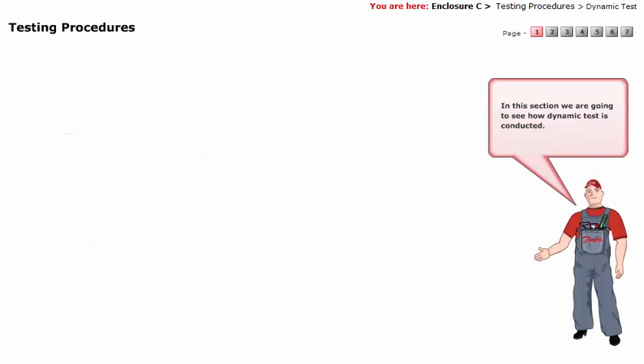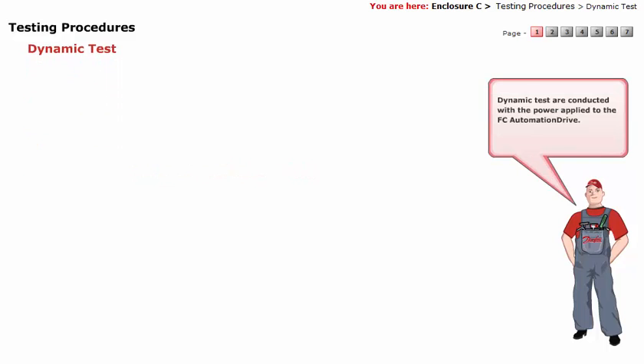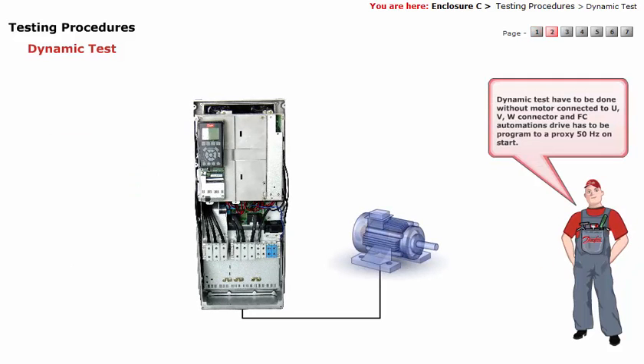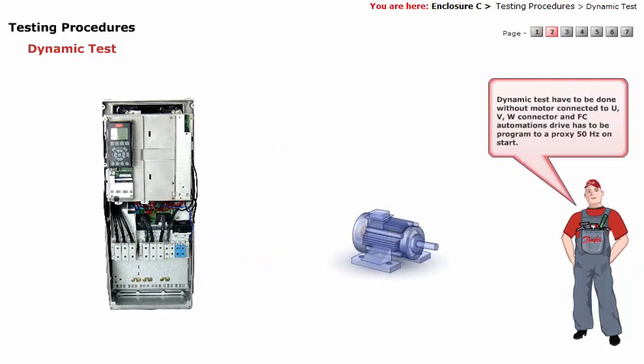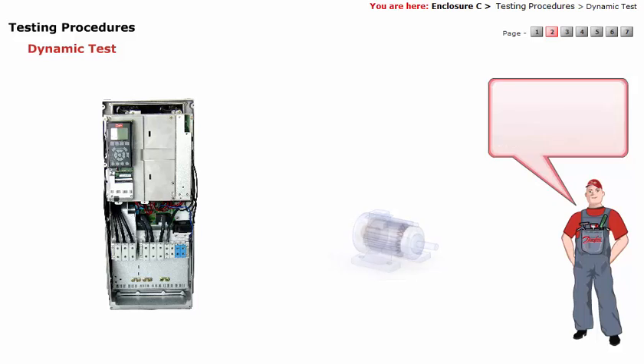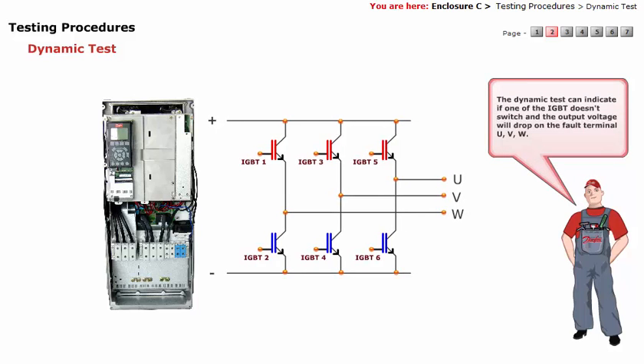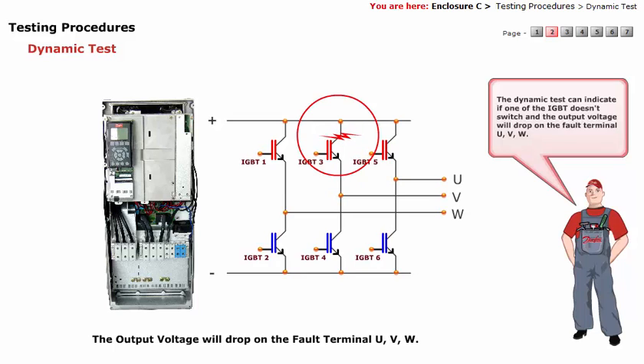In this section, we are going to see how dynamic test is conducted. Dynamic tests are conducted with the power applied to FC automation drive. Dynamic tests have to be done without a motor connected to the UVW connector, and the FC automation drive has to be programmed to a frequency of 50 Hz on start. The dynamic test can indicate if one of the IGBTs doesn't switch and the output voltage will drop on the fault terminal UVW.